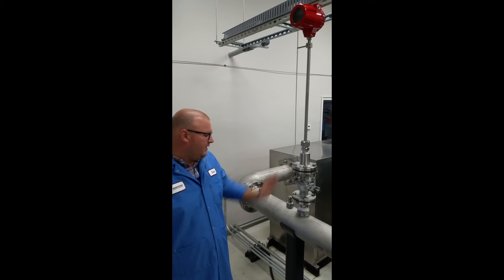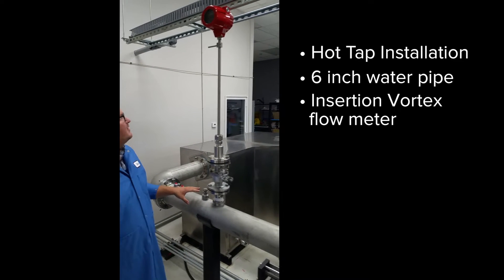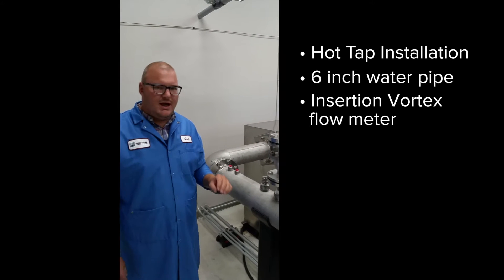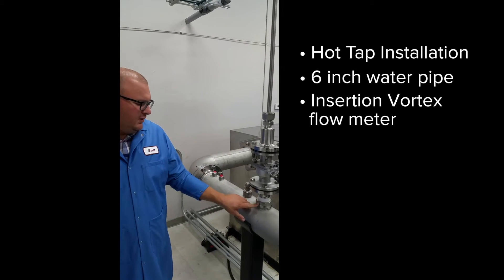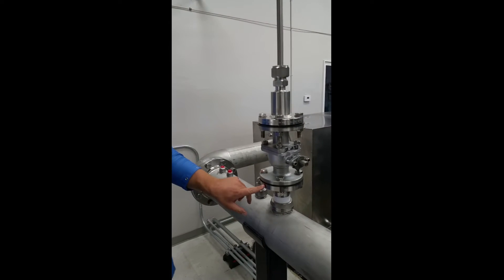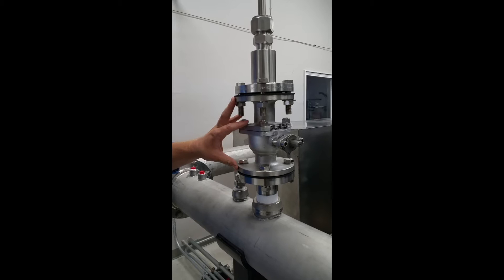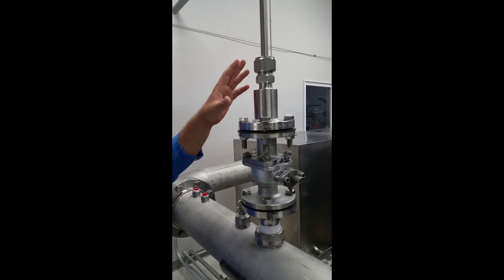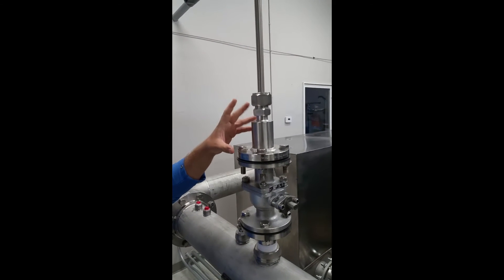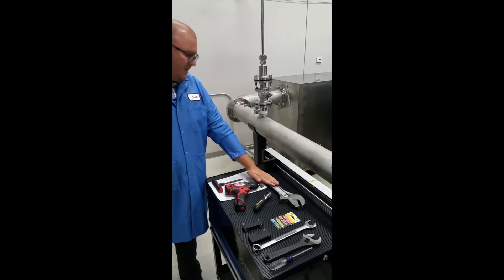We're here today on a 6 inch schedule 40 pipe with water coming through. This would be a typical hot tap installation. This weldlet's been welded into the pipe. We added a 2 inch flange adapter. This is a 2 inch isolation ball valve. And then we have our 241i insertion meter with a packing gland, 2 inch flange packing gland adapter.